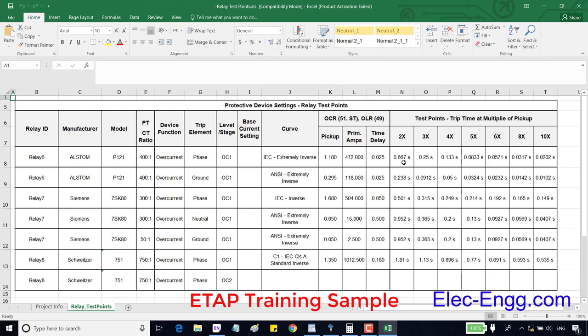If we inject two times of pickup current, the relay should trip at 0.667 seconds. In a real test, we should inject the pickup current, this value.